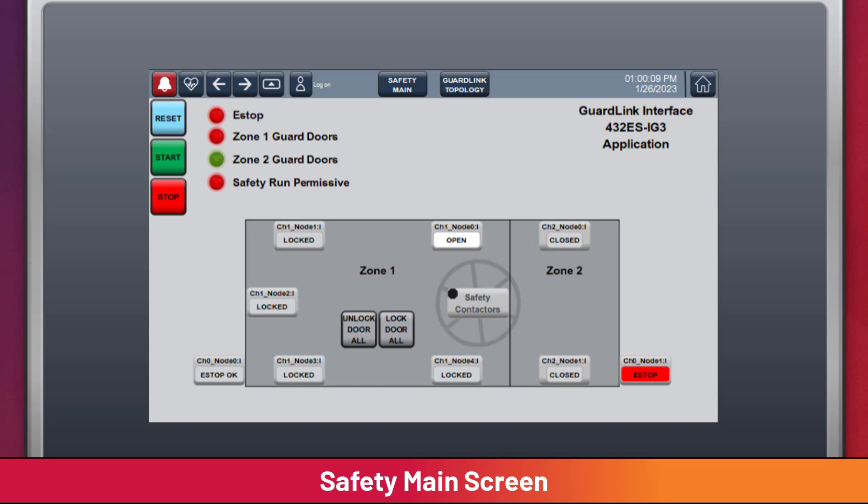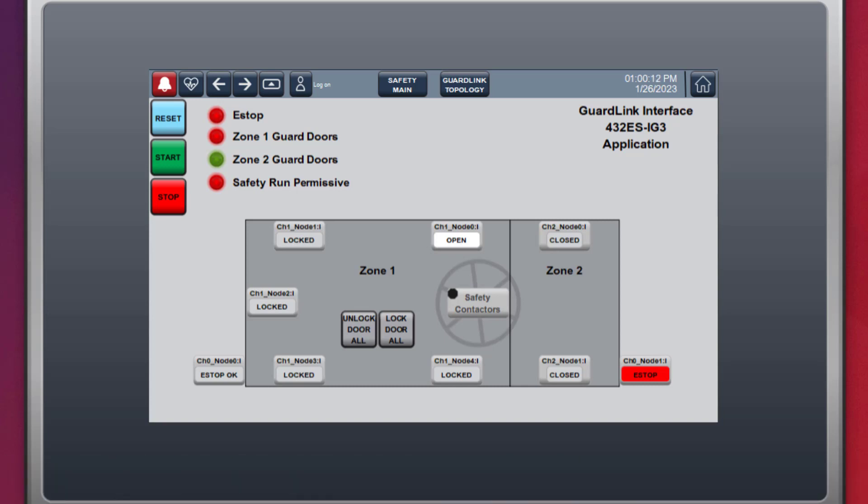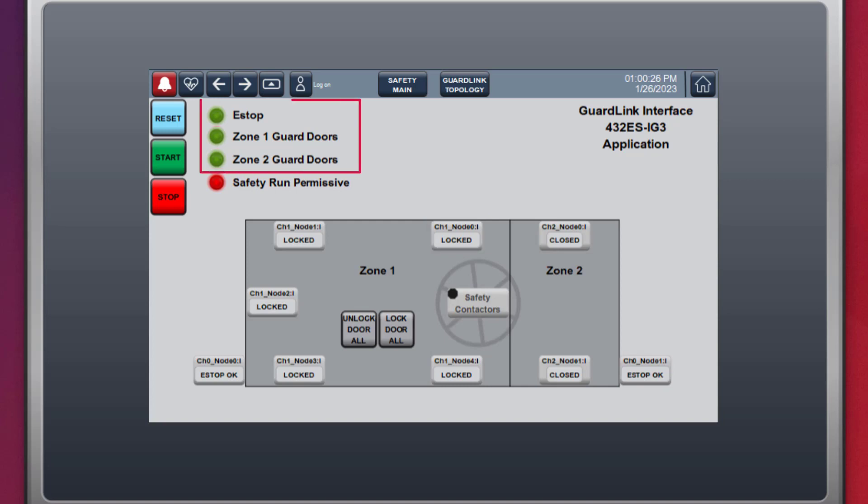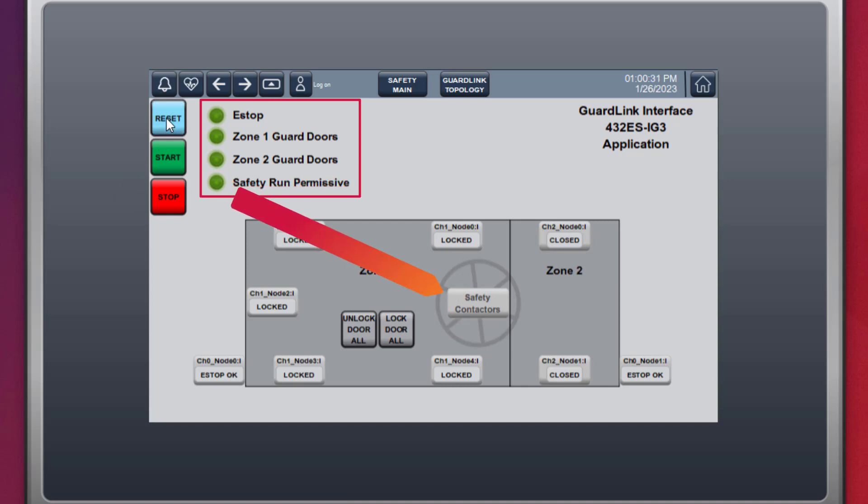During a machine startup, the operator can easily determine which safety devices are tripped. In this case, pull out the e-stop near zone 2, close the locking guard door on the back of the machine. Indicators show e-stops and guard doors are now run ready. Pressing and releasing the reset push button enables the safety run permissive, which energizes the safety contactors. Press the start button to start the machine.